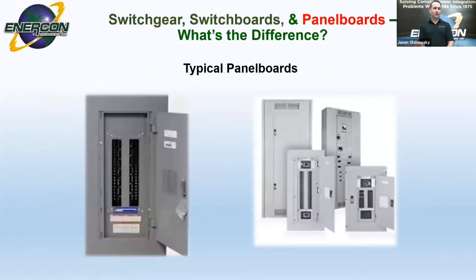All right, so onto the panel board. Here we can see a different range of panel board shapes and sizes. The panel board on your left, this would be what you would see even at your house. We'd be looking at probably a single phase there, 240, 120. So you'd see that for lighting loads and smaller loads. Some of the panels on the right side, where you can see a main breaker, those could be 3-phase, and at 3-phase you'd be running a voltage of 208 and also 120 off the single breaker.